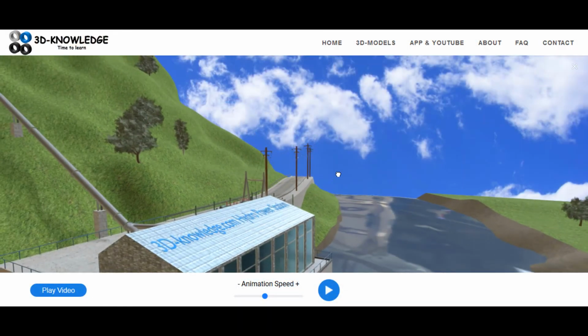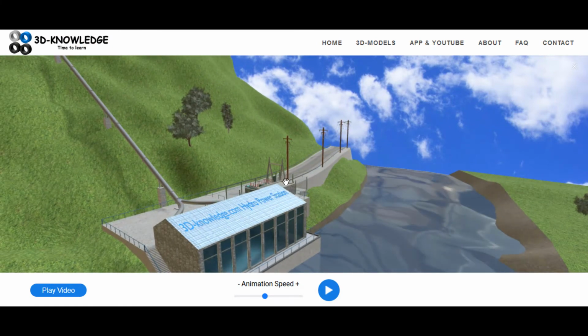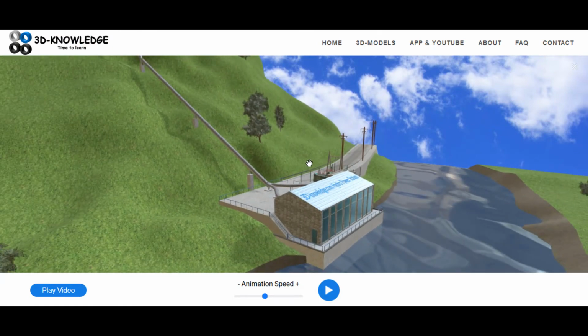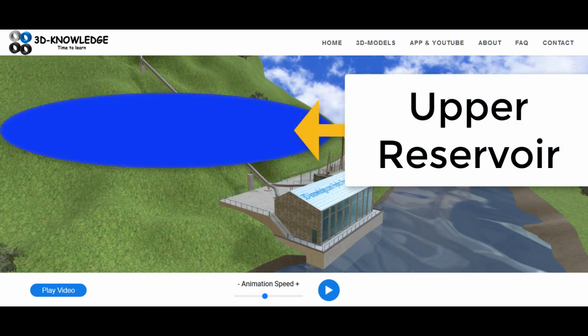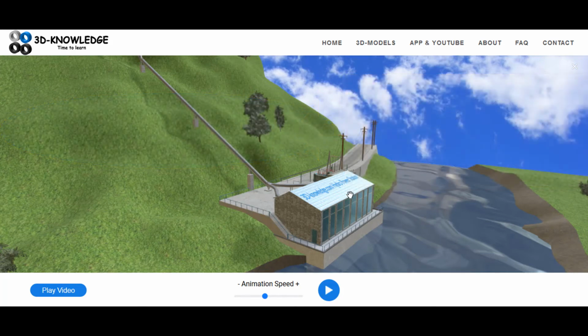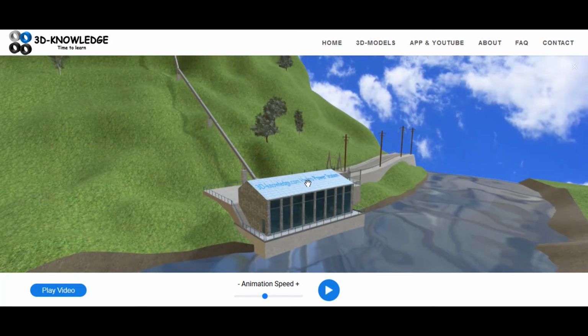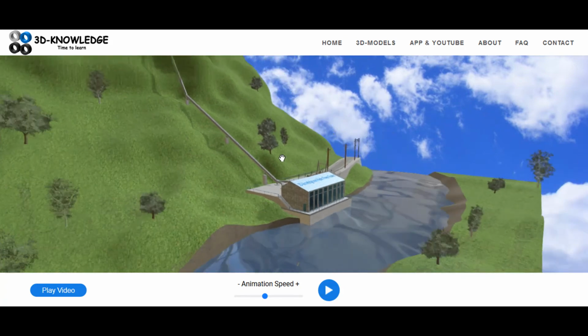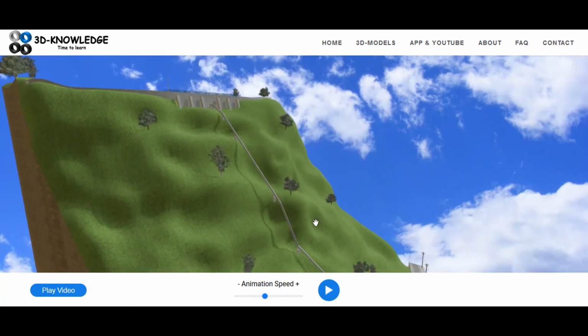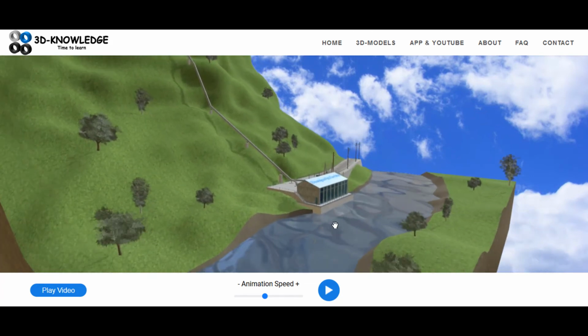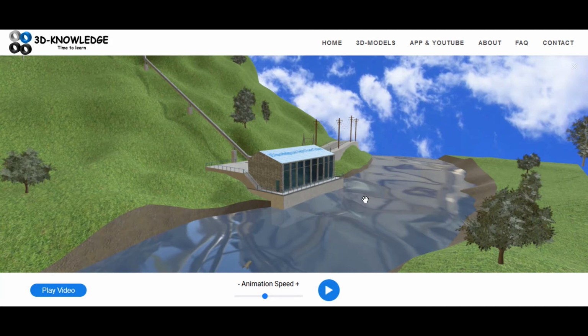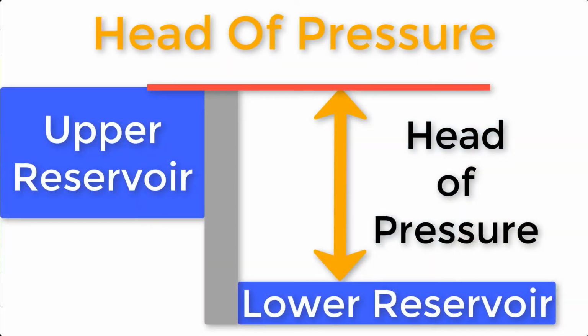But do notice this is a Pelton turbine hydroelectric power station - not a Francis or a Kaplan turbine station. If you had an upper reservoir with only a small amount of head, or a small head of pressure, you would not use a Pelton turbine, since it's not made for low heads of pressure. You really need a very high upper reservoir to get that high pressure to drive the Pelton turbine round and round. If you don't have that head of pressure - which isn't possible in some geographical locations that are very flat with no mountains or hills - then you won't have the chance to use a Pelton turbine.